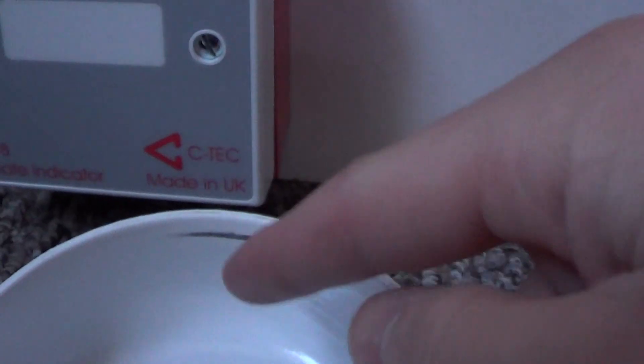If I sound it again, what happens is these weights here spin like this, look, and they hit the gong. You can see where the weights have been striking the bell. They've worn a bit of the paint away. When putting it back you have to remember to locate that little stud on there.